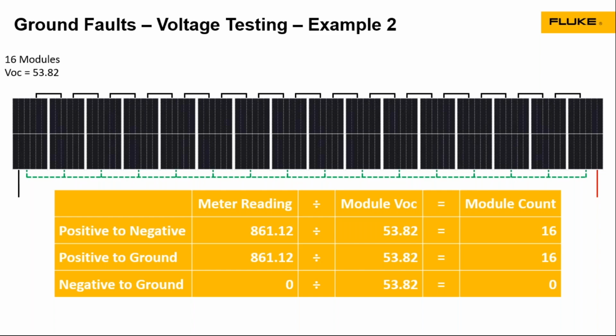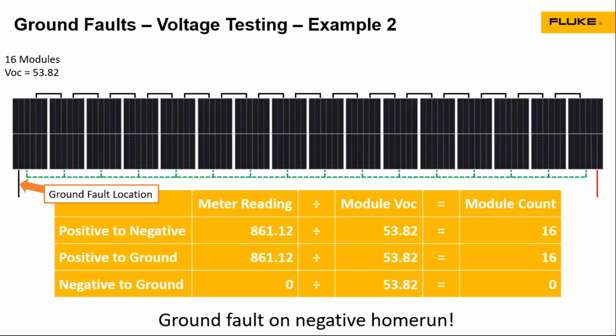What this tells me is that from positive to ground, there are 16 modules between positive and the ground fault, and 0 modules between the negative and the ground fault. That indicates that the ground fault is on the negative home run wire. That's the wire from the end of the string to my combiner box or inverter. This can be a situation that's relatively easy to miss. I'm used to seeing 861 volts and 0. So when you see 861 on the positive to ground, you might miss it thinking that's the positive to negative.